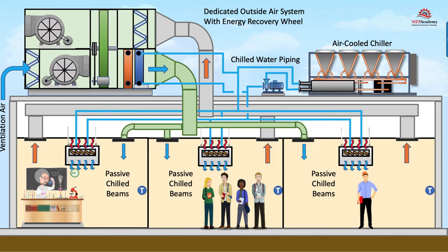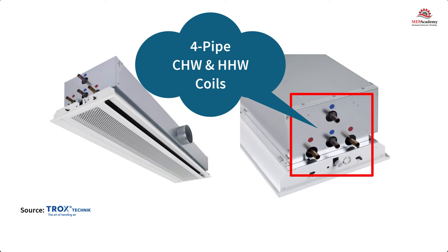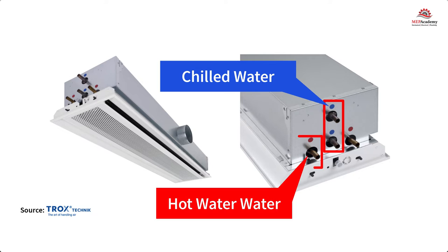Chilled beams have the option of a 2-pipe or 4-pipe configuration, with either a separate heating and cooling coil or a shared coil with the proper control valve arrangement. A 4-pipe system uses 2 separate coils, yielding 4 pipes: 2 chilled water and 2 hot water pipes. The 4-pipe chilled beam will be heavier as there are 2 separate coils.